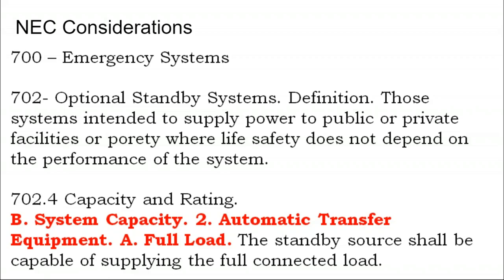There are differences between emergency power systems and standby power systems. Emergency power systems deal with life critical issues, whereas standby power is for when your building loses power and you wait for it to come back on. That might get into redundancy requirements in the power system or the strength of the conduit. So don't be unaware if you're designing an off-grid system and someone's talking about emergency power for medical equipment—you might need to check whether your design is supposed to meet emergency standards or standby standards.